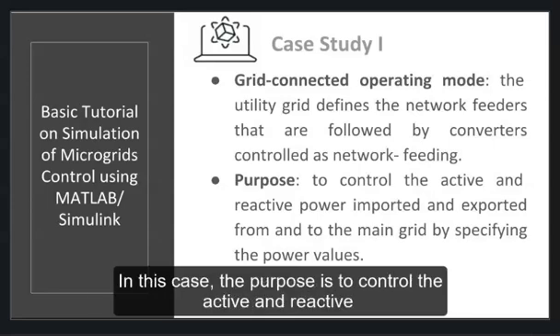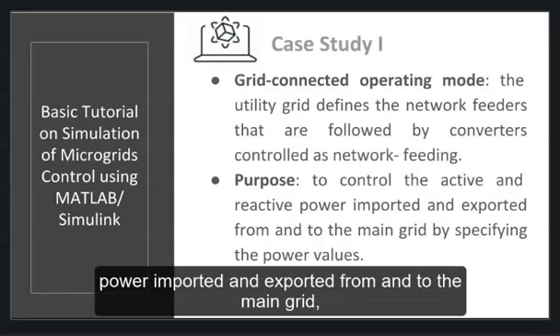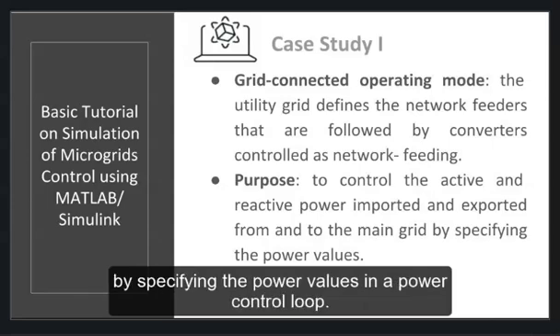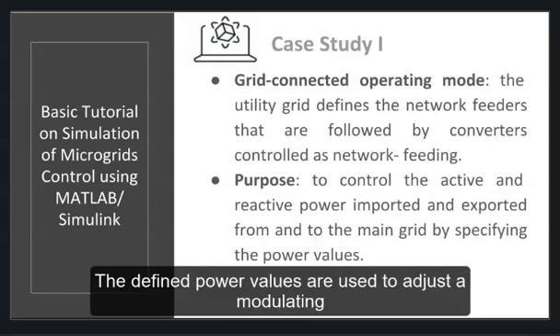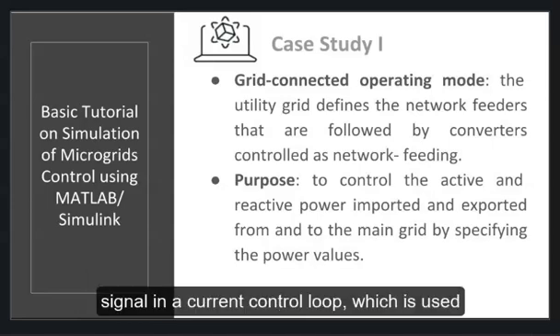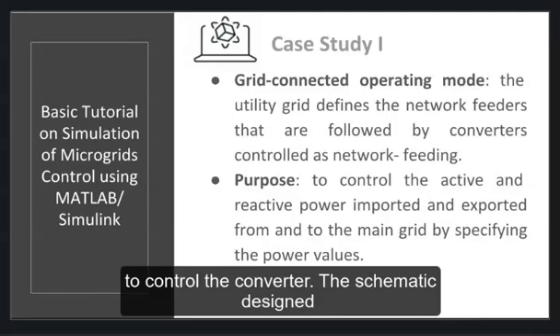In this case, the purpose is to control the active and reactive power imported and exported from and to the main grid by specifying the power values in a power control loop. These defined power values are used to adjust a modulating signal in a current control loop, which is used to control the converter.